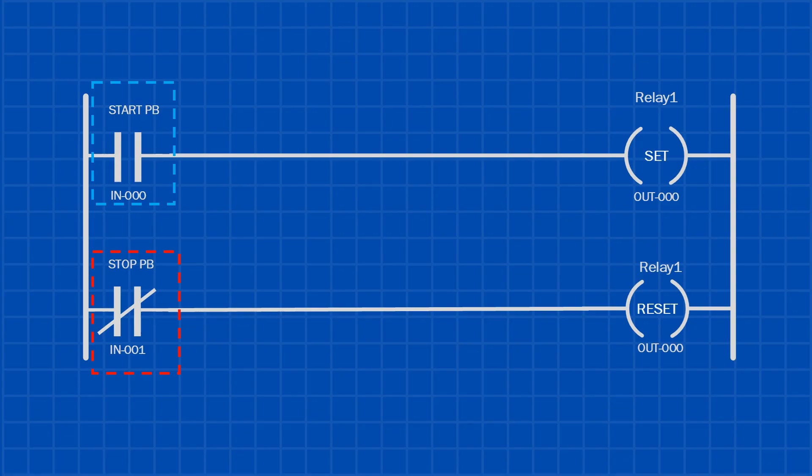Now here's an important detail. In this setup, the stop push button is shown as a normally closed contact in the PLC program. That means it has to open, by being pressed, for the reset instruction to activate.